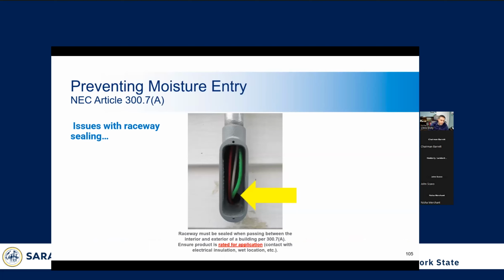Here we have conduit passing from the outside of a building to the inside of a building, and it was not sealed. There's potential for condensation buildup where the warm building air meets the cooler outside air, or vice versa. And once the condensation forms, there's no place for it to go but back into the conduit, and then into whatever panel board or whatever they have inside the wall there. And again, you want to avoid any moisture getting into these situations, because it can cause massive problems with your electrical. And this is not just a violation of the electrical code, it's also part of the energy code. So since there's an energy component to it, if they sealed that, then there would be basically no flow of air and no potential for condensation.